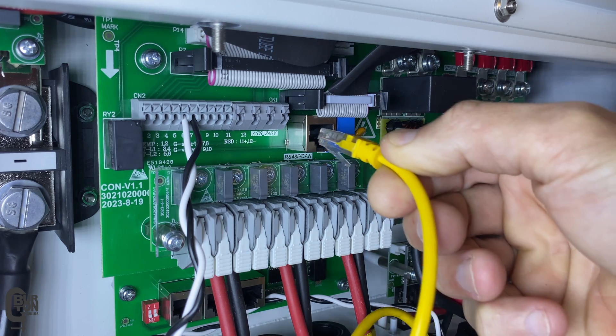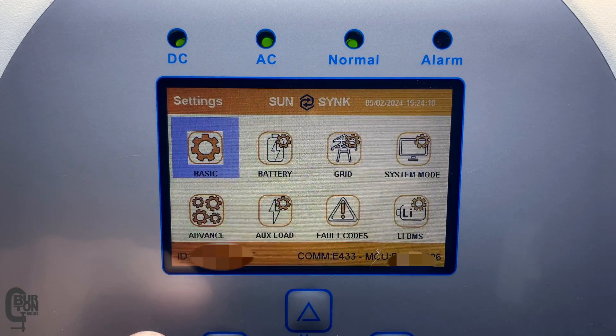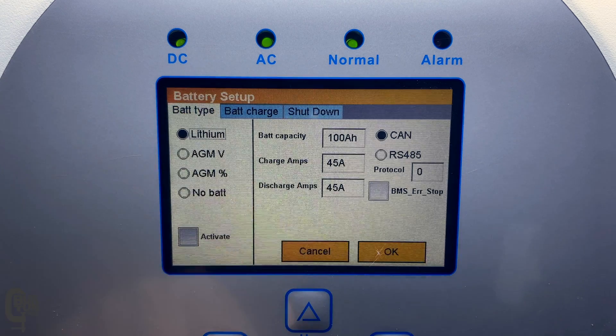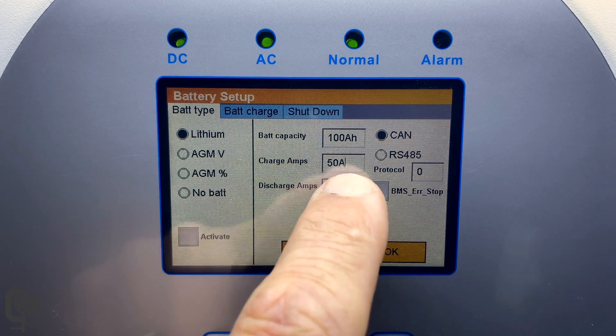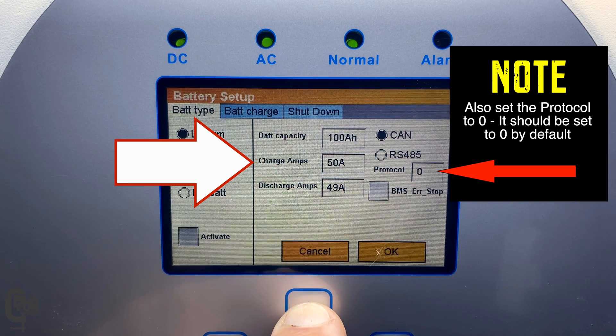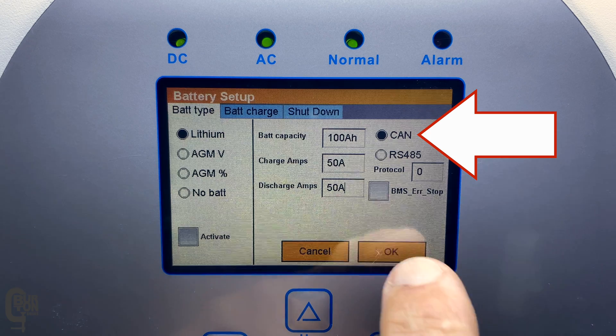Just to note, this yellow Ethernet cable is the cable that came with my Sunsynk inverter. In the settings menu on the inverter, select battery and then battery type. On this screen select lithium, select the battery capacity, the maximum charge amps, and the maximum discharge amps, and then select CAN and click OK.